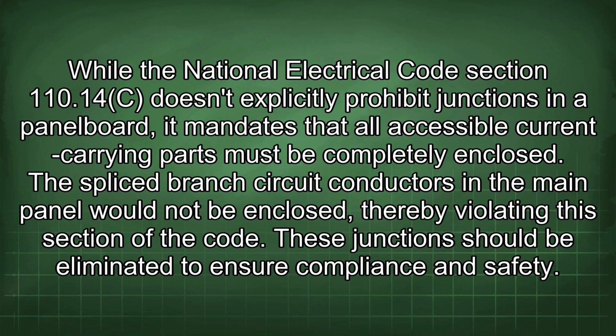While the National Electrical Code Section 110.14(c) doesn't explicitly prohibit junctions in a panel board, it mandates that all accessible current-carrying parts must be completely enclosed. The spliced branch circuit conductors in the main panel would not be enclosed, thereby violating this section of the code. These junctions should be eliminated to ensure compliance and safety.